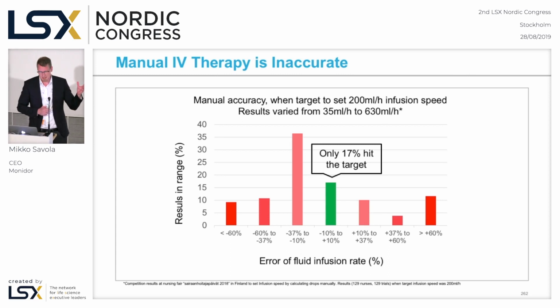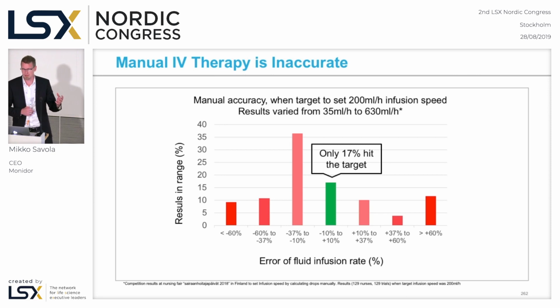This picture shows results when 129 nurses try to set 200 mils per hour, which is a typical infusion rate on a general hospital ward. Only 17% of the nurses could reach 10% accuracy. But look at the extremes. It is alarming how many could not even reach 60% accuracy when doing it like educated in nursing school.